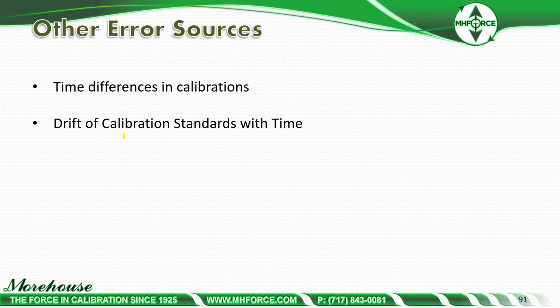And then also you have the drift of calibration standards with time. That's covered a little bit earlier. People say they can age things, this age dating or whatever, it doesn't really work that way. If I calibrate a load cell to 10,000 pounds today and put it on a shelf for 2 years, it's naturally going to age and shift over time. So it's very mechanical in nature. Aged load cells are better than non-aged ones. So that's something else to consider.